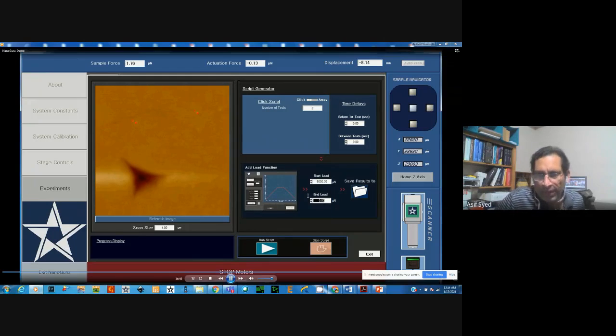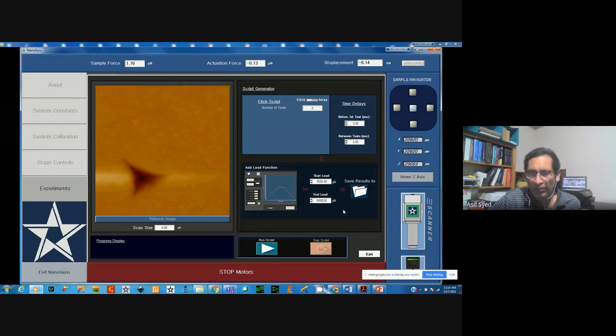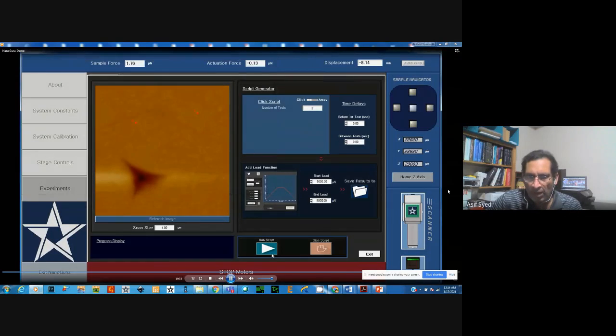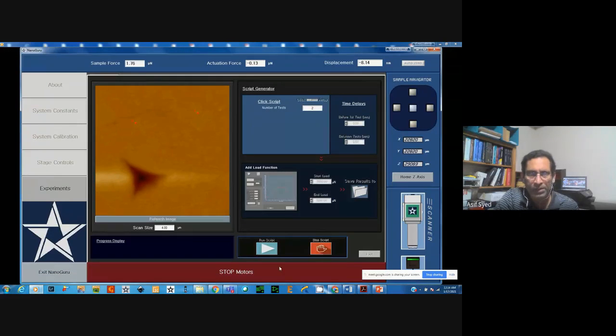The way it works is you start with one load and then go to the next load progressively up to the maximum load, that end load. So I'll use the same 5,000 micronewton load for the first indent, and the second also 5,000 micronewton, and then save the file as a demo file. Now, if I click the run script button, it will automatically start doing those experiments at those two locations.